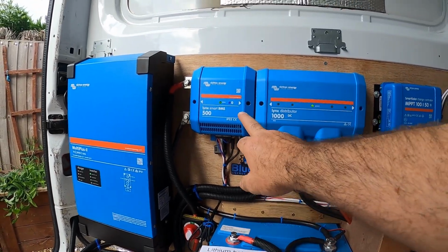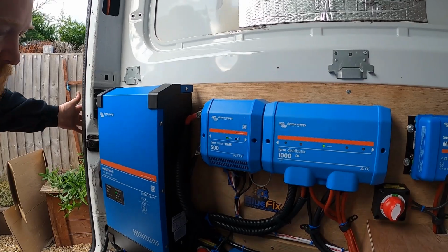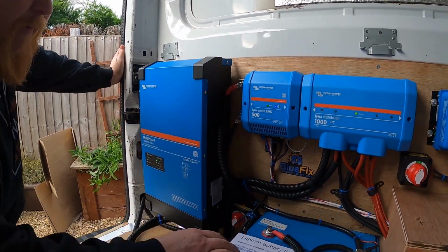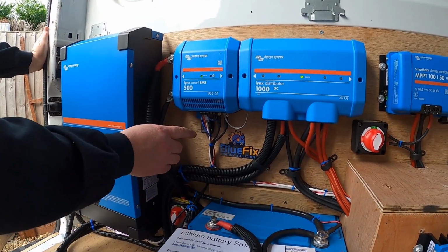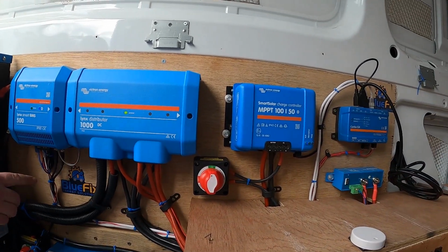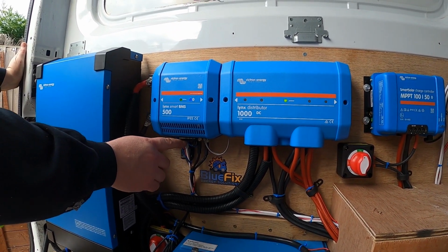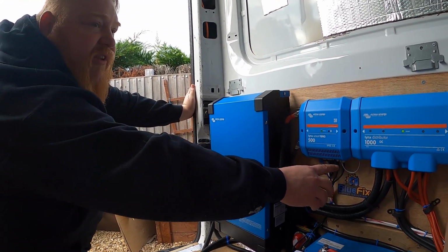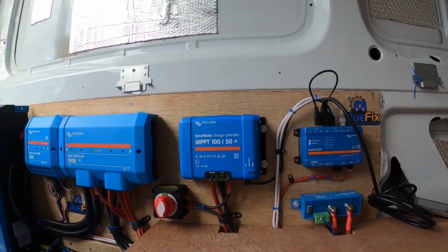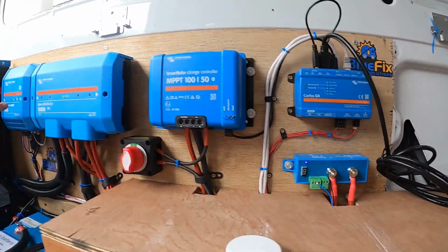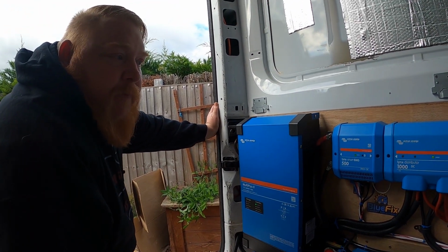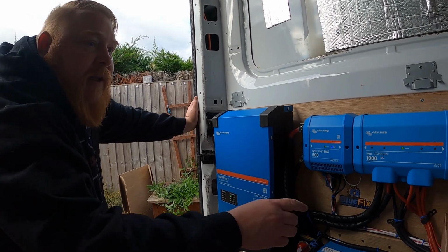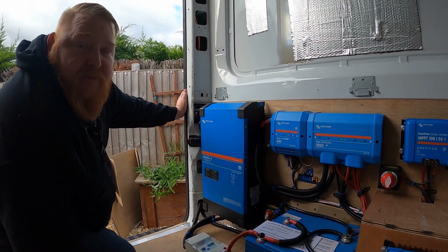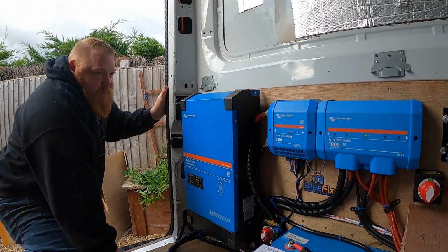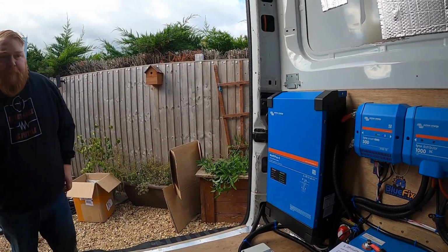We've got the Lynx Smart BMS - it's a lovely bit of kit. This talks to the batteries via the system here, but it has a power out for our Cerbo GX, which is constant power, which also links through to pins 5 and 6. Pin 5 comes in, 6 goes out, which is the exciter wire for the high cutoff for allowed-to-discharge on the battery protect there. So should this decide the batteries are too low and we need to conserve power, it'll turn the loads off - the allowed-to-discharge will switch off. It's a very clever bit of kit, quite a bit of money, but I've got this one in my van and it's definitely worth it, I think.